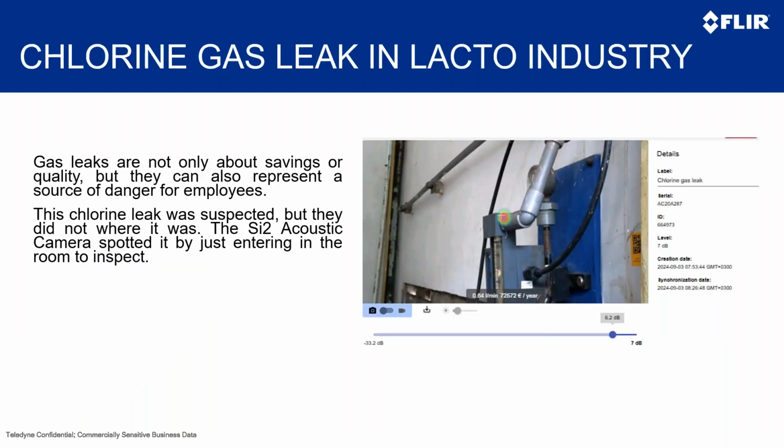This is another example. This is a chlorine leak in an industrial facility where they knew that there was a chlorine leak because they could smell it, but they didn't know exactly where it was. Of course, they could use other methodologies, but they said, well, we can check with the camera now because we know that there is something going on here.